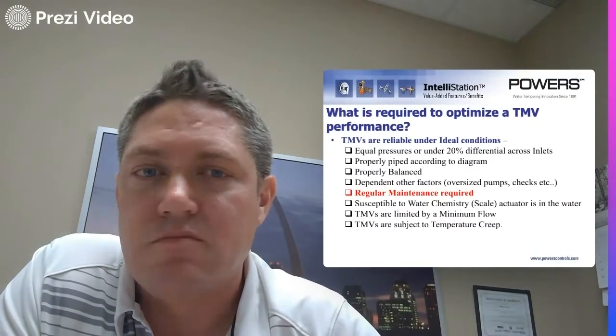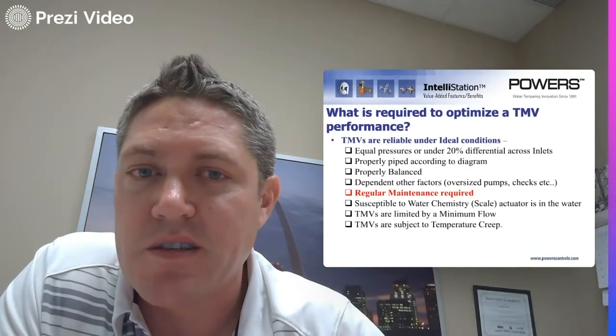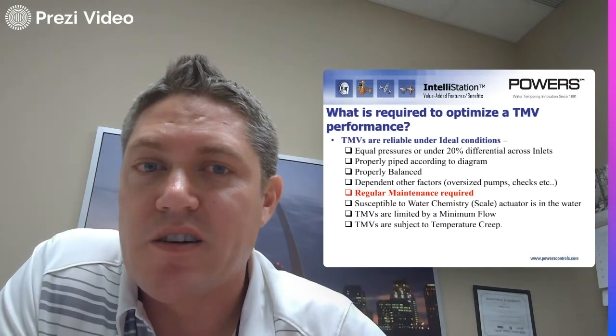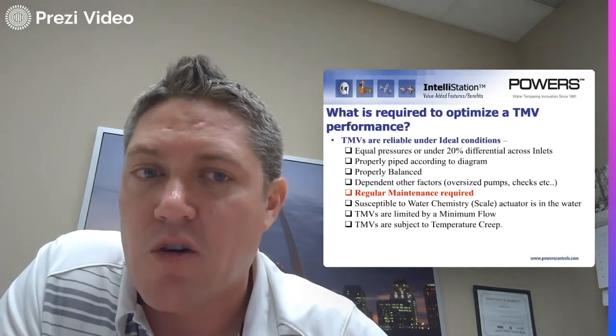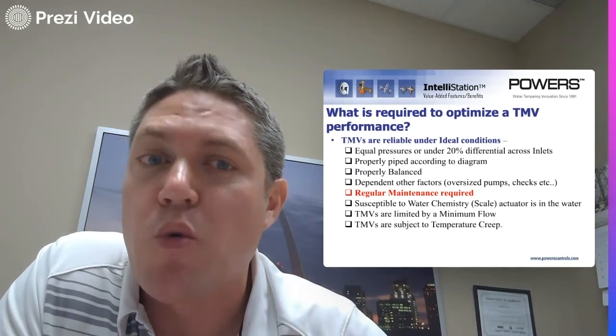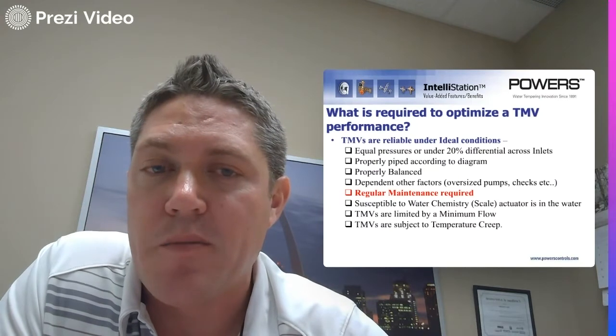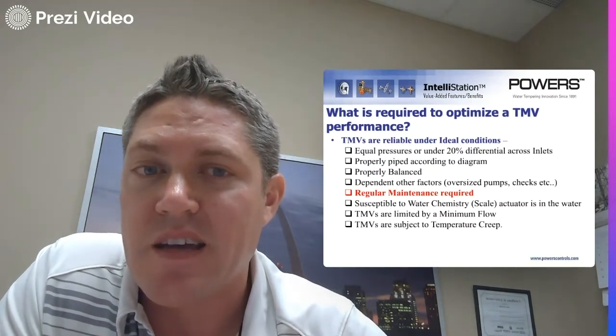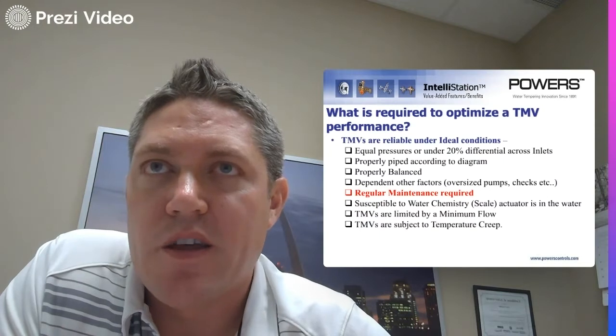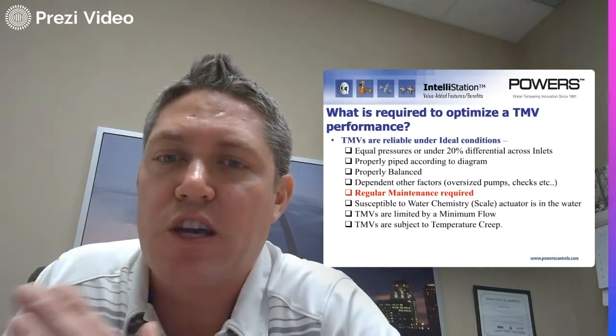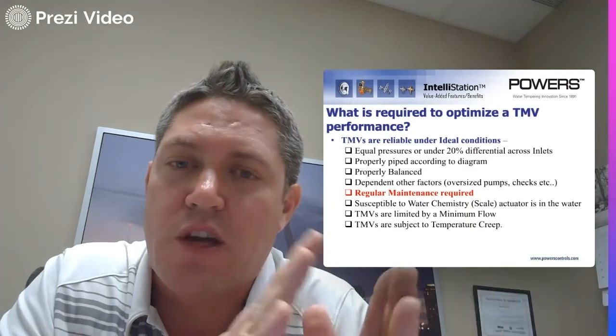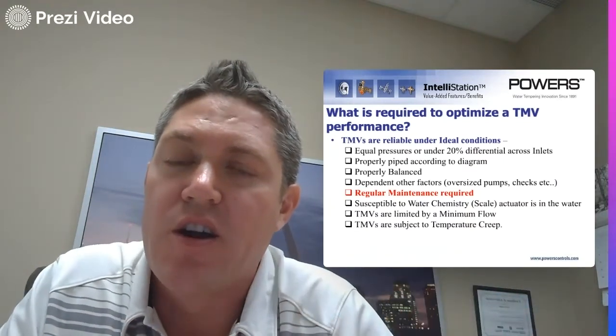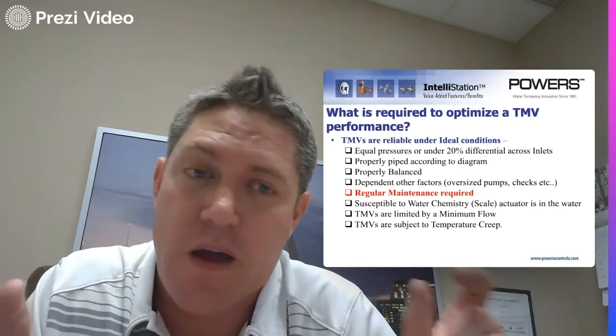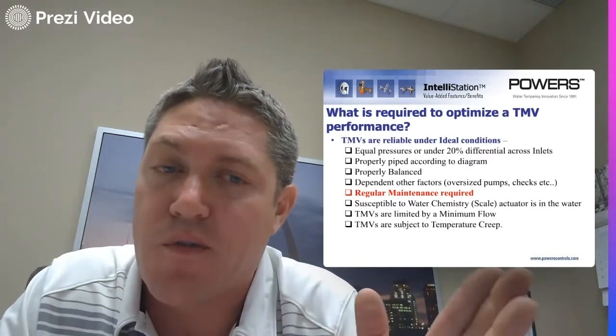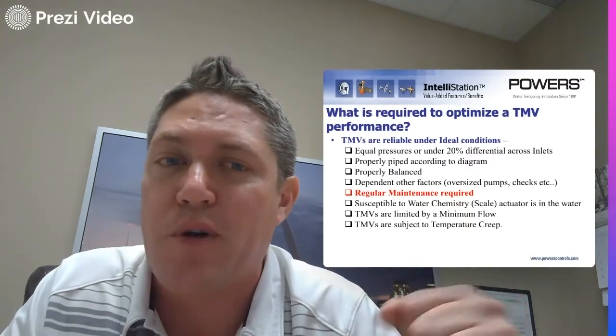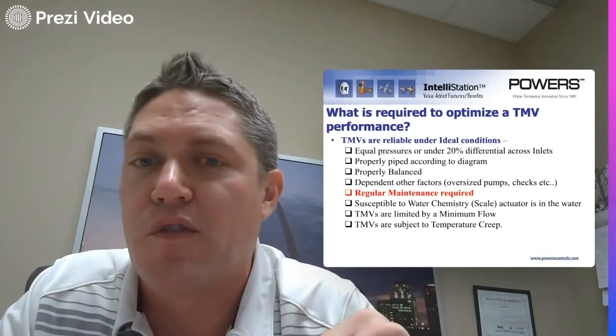Okay, so let's talk about thermostatic mixing valves and their performance. Here are some of the fallbacks. You have to have equal pressures across hot and cold inlets. They have to be within 20% differential of one another to be able to appropriately mix and hit set point. With a thermostatic mixing valve, you're never going to get it to fully close off hot or fully close off cold. It only closes off about 80% one way or the other. So if you still have an opening on either side, even if you're trying to go full hot or full cold for the set point of that mixing valve, if the pressure differential is too great, then it'll just overcome the other side, hot or cold.